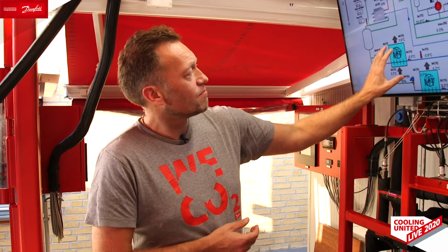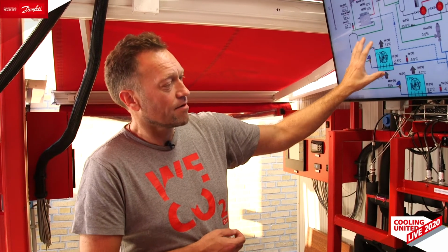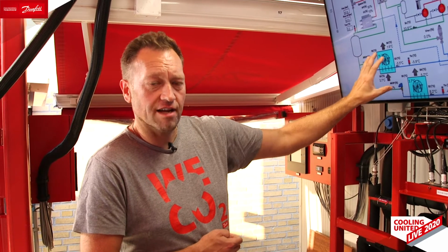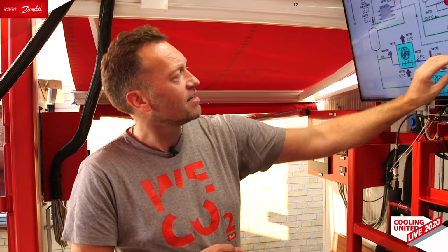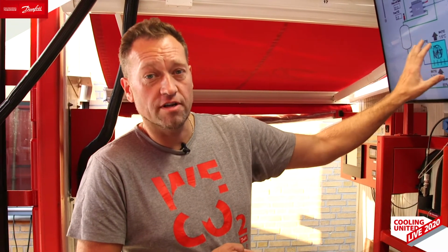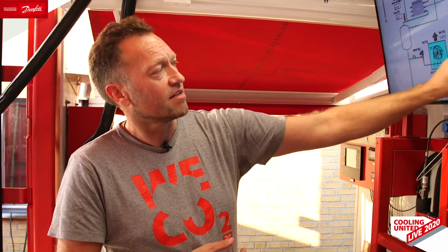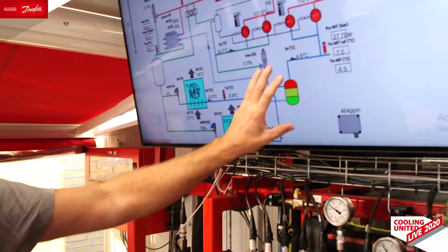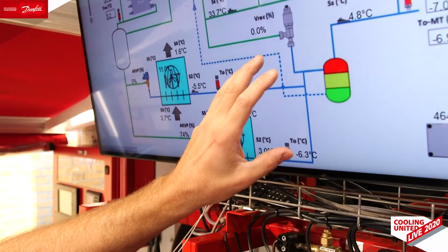The reason why we only have very little refrigerant coming back to the system is that we are running close to this 0 Kelvin, and this means that there's only droplets coming out of the evaporator. And if you have a system with 10 or more evaporators, then you will typically have a quality of the refrigerant at the accumulator of maybe 3% liquid.